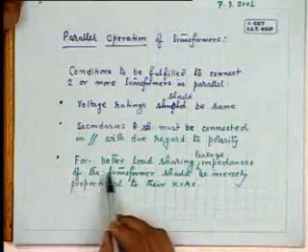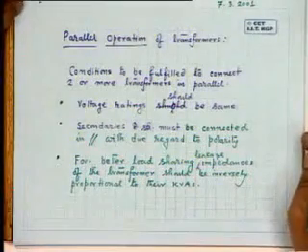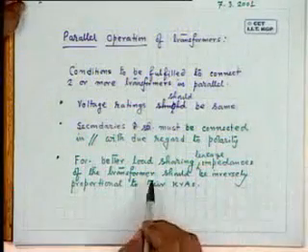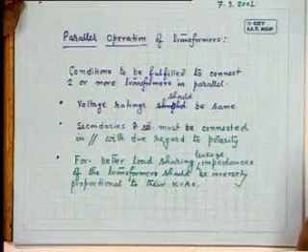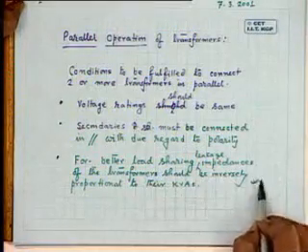And the third point is, for better load sharing, the leakage impedance of the transformers should be inversely proportional to their kVAs. This point I will discuss in detail.